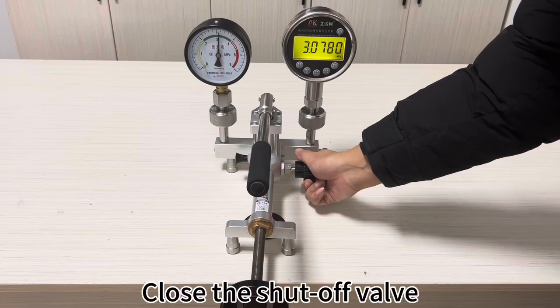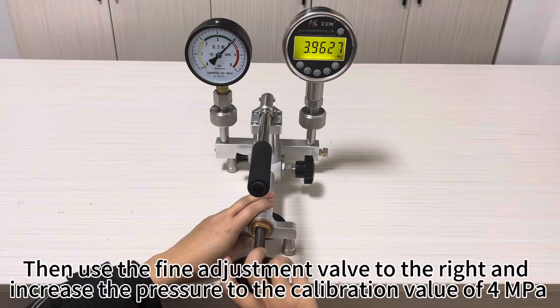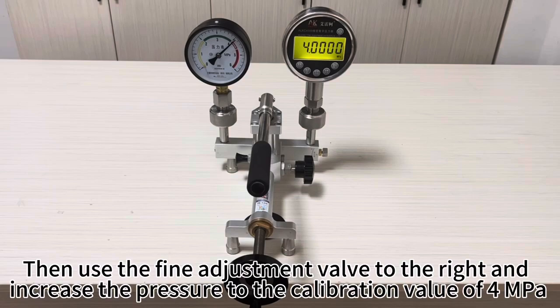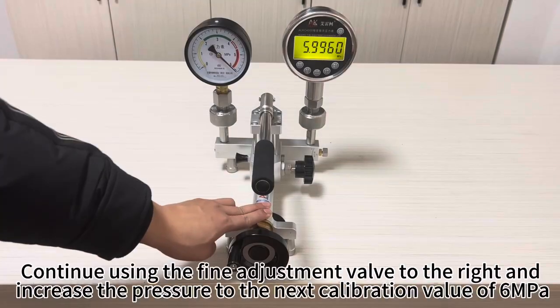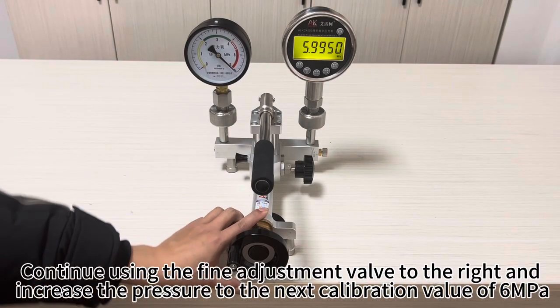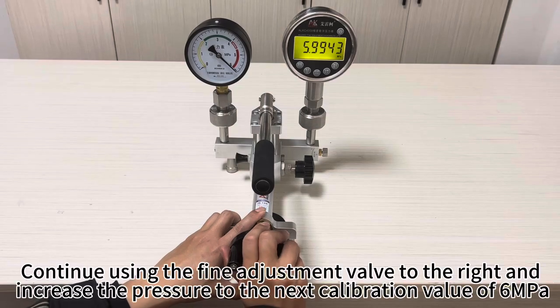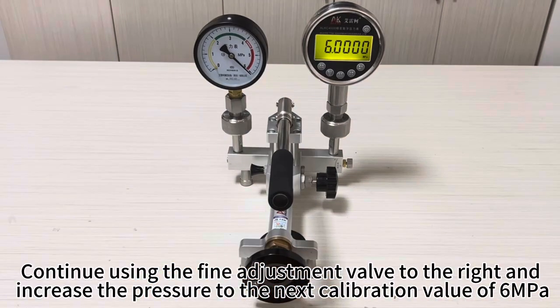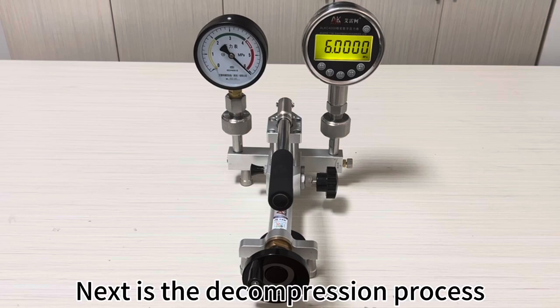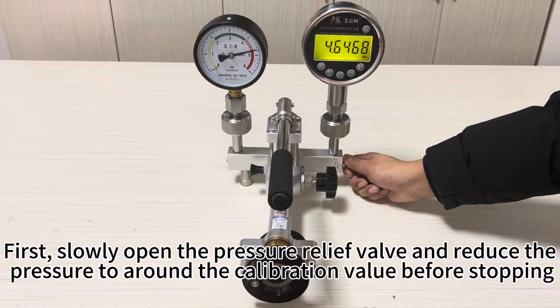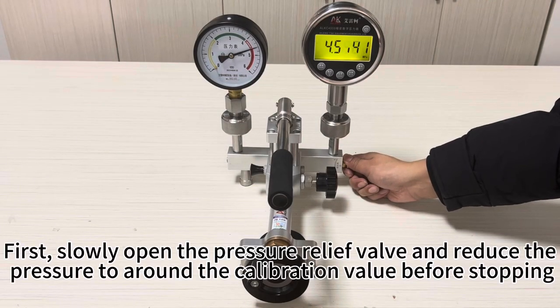Close the shut-off valve. Then use the fine adjustment valve to the right and increase the pressure to the calibration value of 4 MPa. Continue using the fine adjustment valve to the right and increase the pressure to the next calibration value of 6 MPa. Next is the decompression process. First, slowly open the pressure relief valve and reduce the pressure to around the calibration value before stopping.